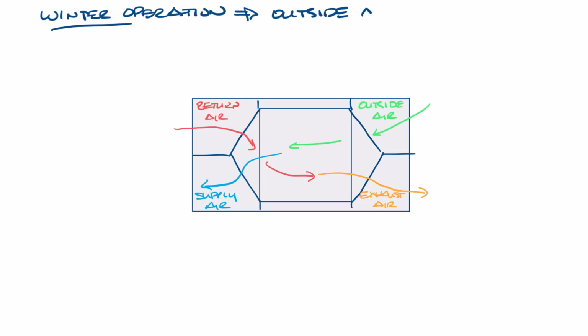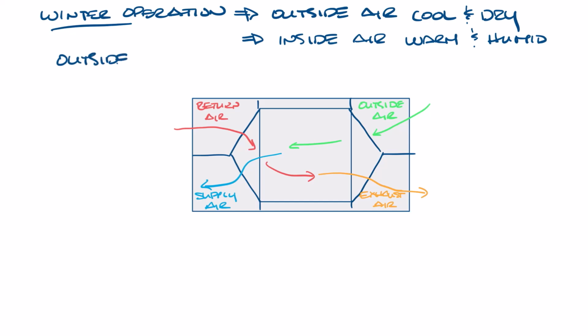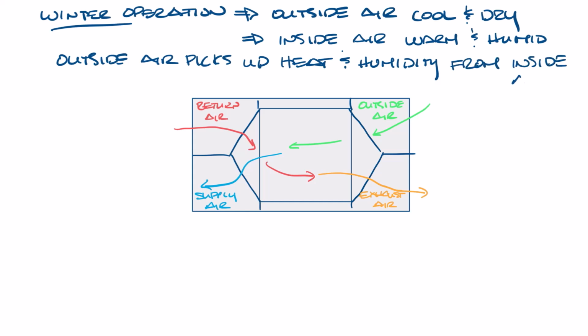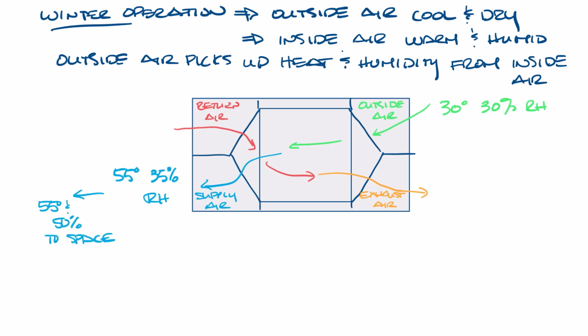In the winter, the outside air is cool and dry, but the inside air is warm and humid. So the outside air picks up heat and humidity from the wheel or the plate that was left there by the return air and supplies it back into the space. So the outside air can come in at, say, 30 degrees and 30% humidity, pass through the heat exchanger and is now 55 degrees and 35% humidity. Then it goes to the space at 55 degrees and 50% humidity. So it's either heated or cooled to get to the space.